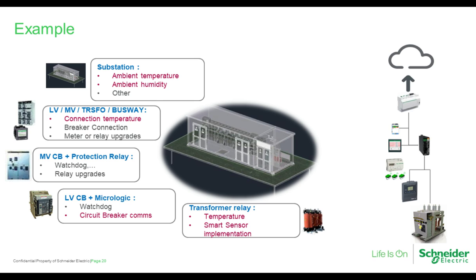On the medium voltage side, we can upgrade that by adding new protective relays, as we indicated before, like replacing the old electromechanical relays on a door with a new solid state relay. We can also look at adding power monitoring, and we can also replace that old air magnetic breaker with a new vacuum replacement breaker, and upgrade the safety of that system, both from a protective situation and from an arc flash situation. And again, we've got other devices within the low voltage breaker that can actually send information back to a system to see what's going on in the system.